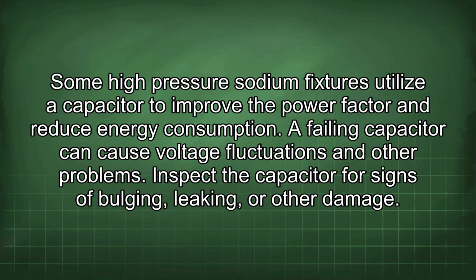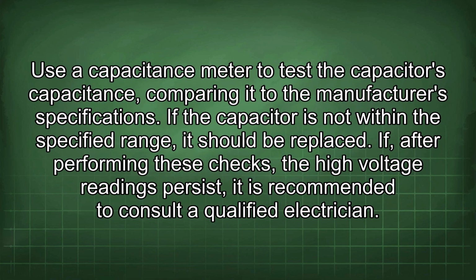Some high-pressure sodium fixtures utilize a capacitor to improve the power factor and reduce energy consumption. A failing capacitor can cause voltage fluctuations and other problems. Inspect the capacitor for signs of bulging, leaking, or other damage. Use a capacitance meter to test the capacitor's capacitance, comparing it to the manufacturer's specifications. If the capacitor is not within the specified range, it should be replaced.